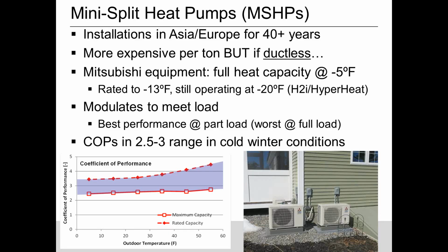So, the builder's experience with these mini-split heat pumps. Transformations builds very low load houses in the 10 to 18,000 BTU per hour heating design load range. So this is well below what even the smallest furnaces out there are. The smallest furnaces I've seen are 40,000, maybe they modulate down to 30,000. All of their production uses these mini-split heat pumps as the single source of heating with no backup. Typically one per floor, so two for an 1,800 square foot two-story house.